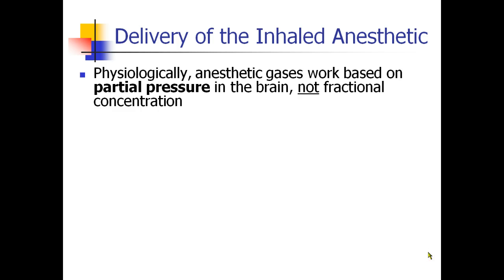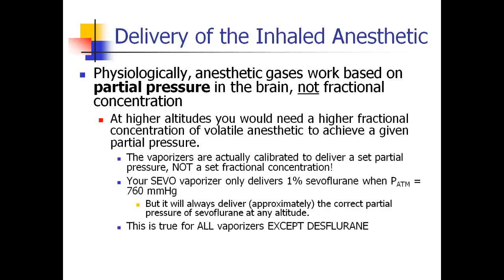Physiologically, these gases work based on partial pressure in the brain, not fractional concentration. Your brain needs 7.6 mmHg of isoflurane, not 1%. At higher altitudes, you need a higher fractional concentration to get that same partial pressure. If you look at your sevoflurane vaporizer, it's calibrated at 1%, 2%, and so on — but actually it's calibrated to deliver a set partial pressure. It only delivers 1% sevoflurane when atmospheric pressure is 760 mmHg. If you take that vaporizer up to Denver or somewhere with very low atmospheric pressure, it will still deliver 7.6 mmHg of sevoflurane, but it won't be 1% even though your dial says 1% — it'll be 2%. This is true for all of our vaporizers except desflurane, which we'll discuss more later.